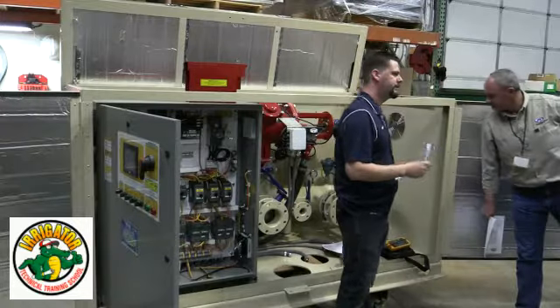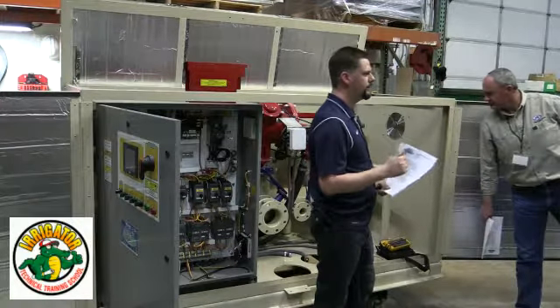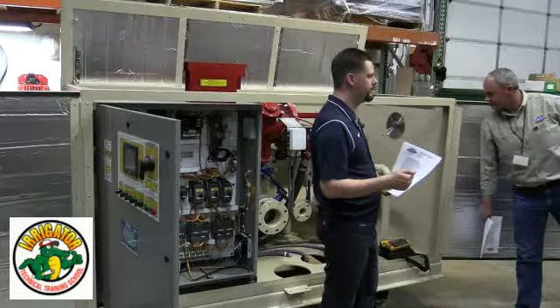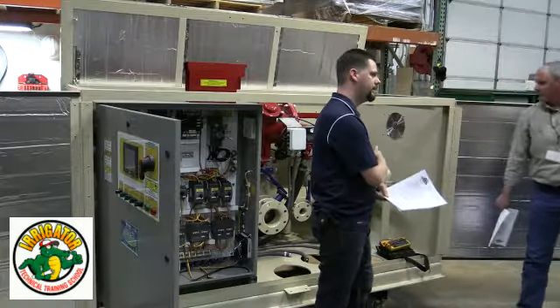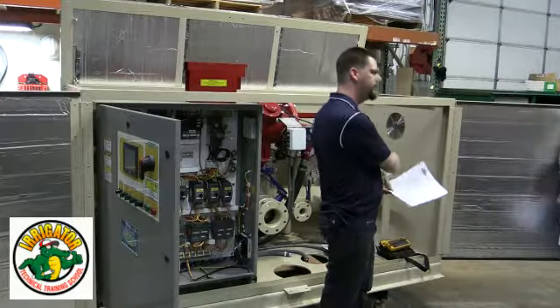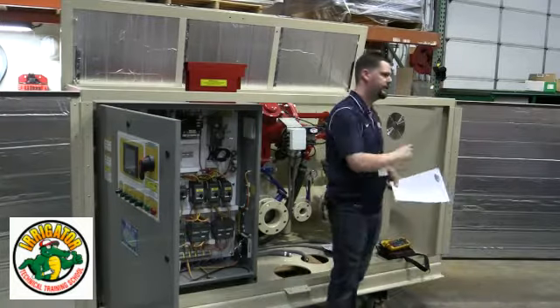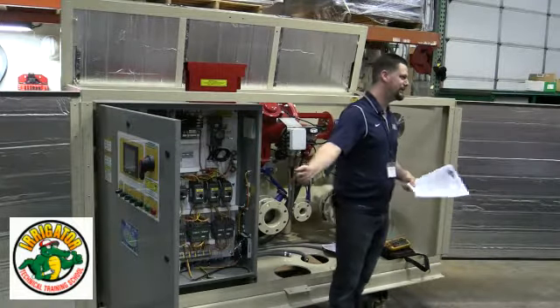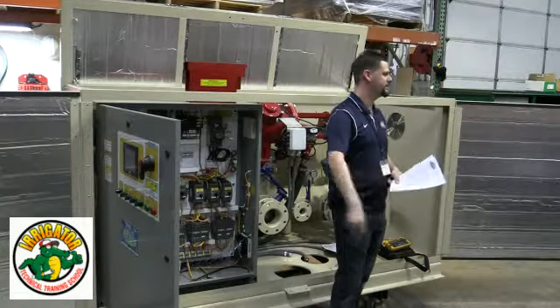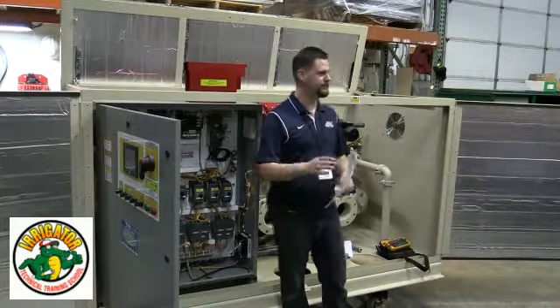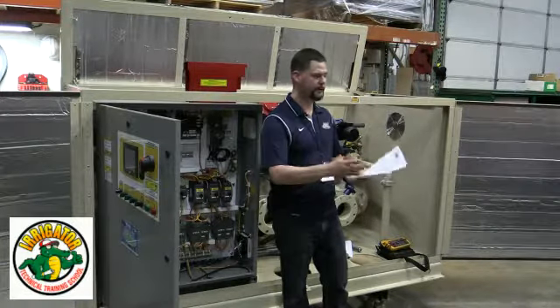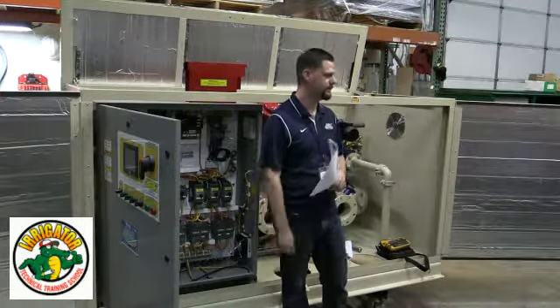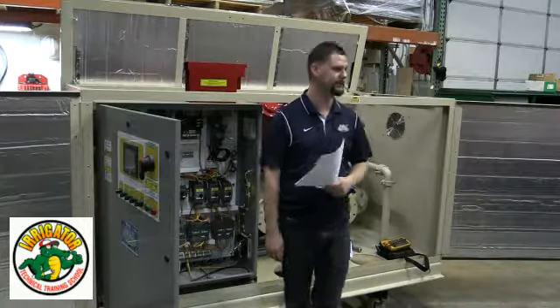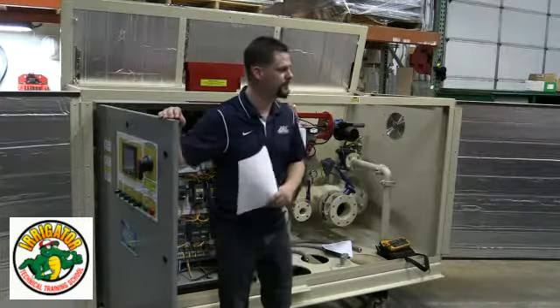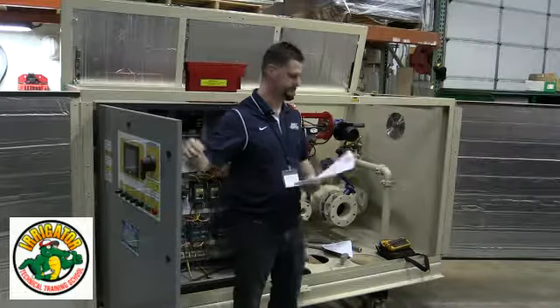Oh yeah, another thing is when you're running the pumps on the drive, let's say you have a centrifugal pump, you can see the rotation. When you go across the line, you want to make sure it's actually still going that direction, because the drive creates basically new power and can go whatever direction you tell it to. It doesn't necessarily know which direction that is other than forward or reverse.